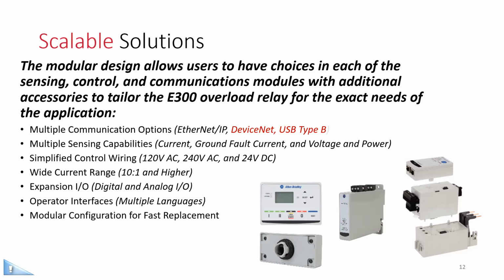E300 offers an expansion bus in which we can add additional digital I/O, analog I/O, and operator stations to the base E300 system without the need for any additional communication address. The diagnostic station does support multiple languages, and the operator station does fit into a standard 22 millimeter knockout. So no need for a special knockout.